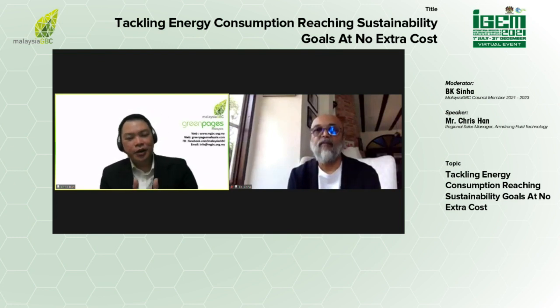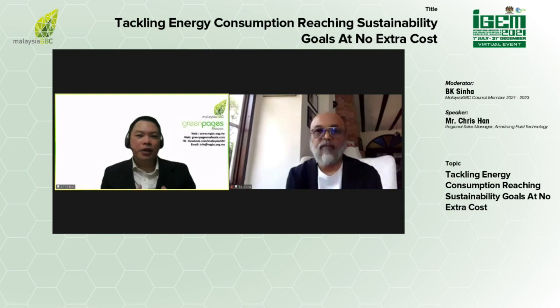If the chillers are operating for long hours of the year at very low load conditions, the cooling tower water temperature during those hours can be reduced. So you really need to compare the economics of adding a VFD to the chiller versus using the same amount of money to purchase a high efficiency chiller.